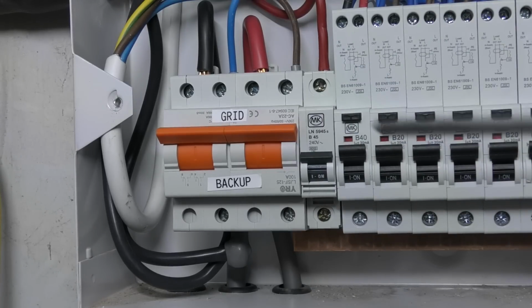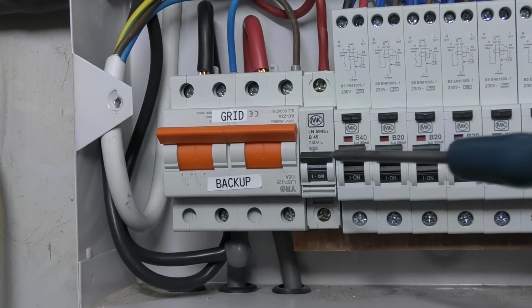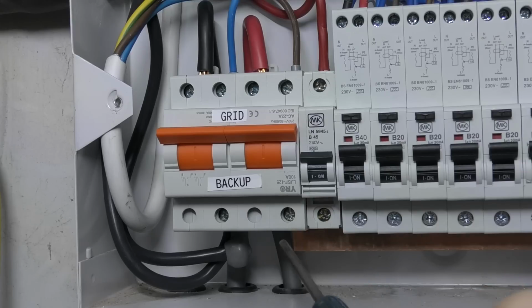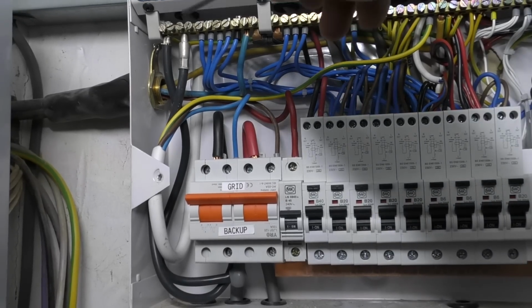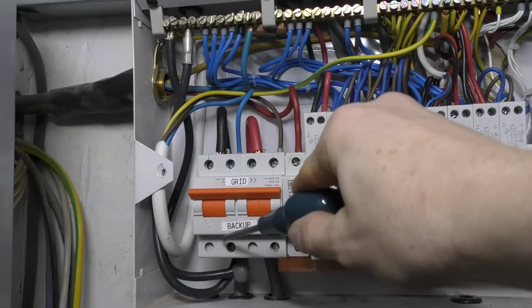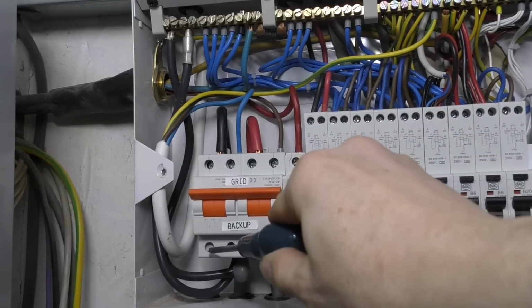Unfortunately, just because of the way this is arranged, I actually had to mount this upside down to get the live out to match up with the bus bar. And this is just a copper bus bar that feeds all the other breakers. This unit also had a copper bus bar that went up from the neutral bar down into the neutral out, but because of this distance here, that wouldn't fit, so I just replaced that.